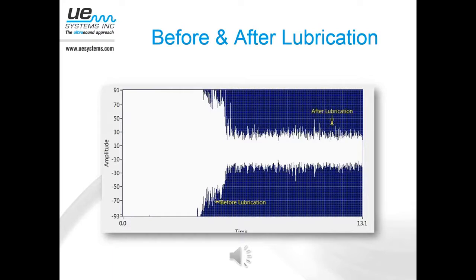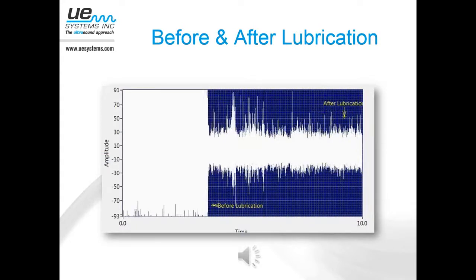If you're using one of the ultra probes, you'll either see the spectrum or the time waveform on the back of the 15,000, or you'll see the dBs drop on the digital grease caddy. So you can see it's a very abrupt, dramatic change from when it needs lubrication to when that lubrication hits the wear surface.